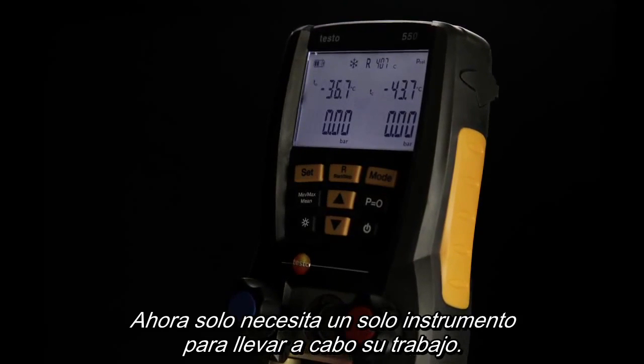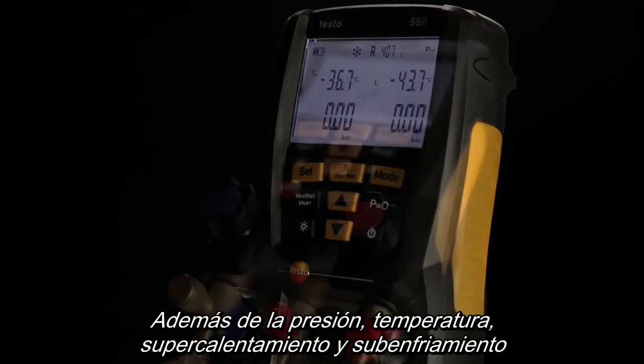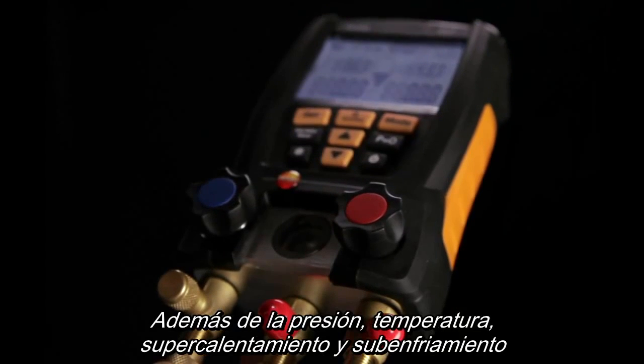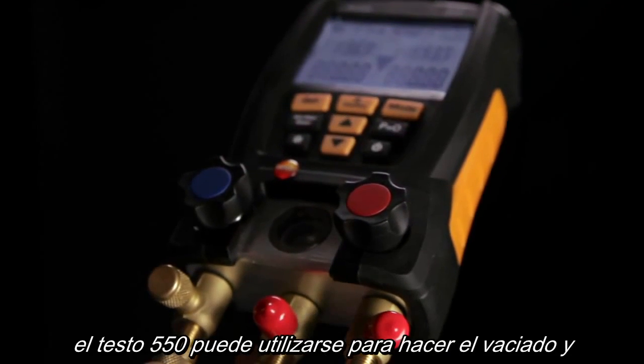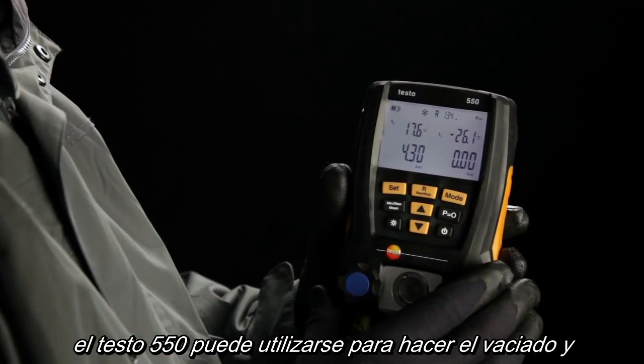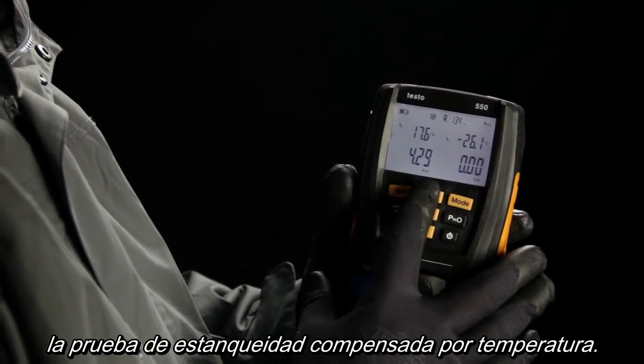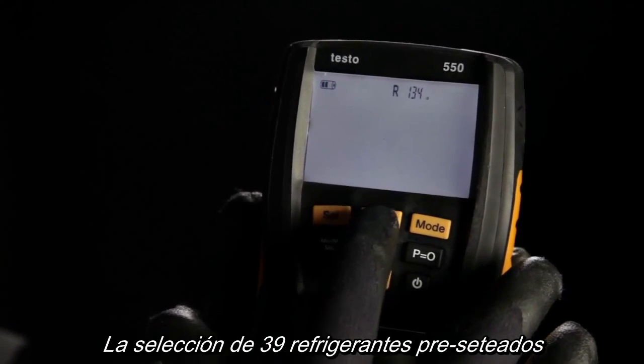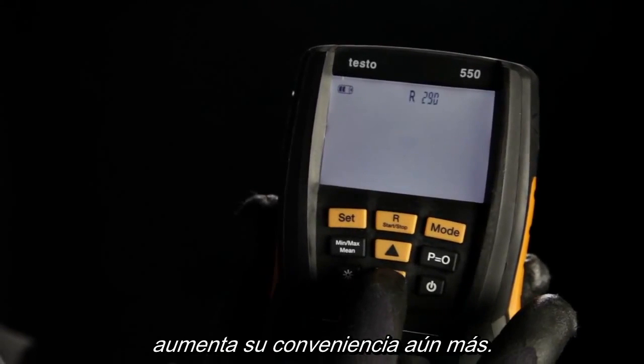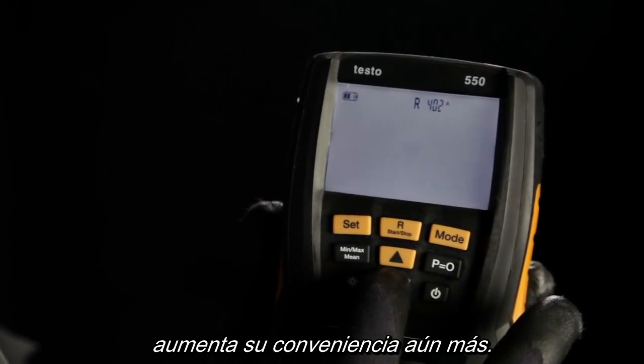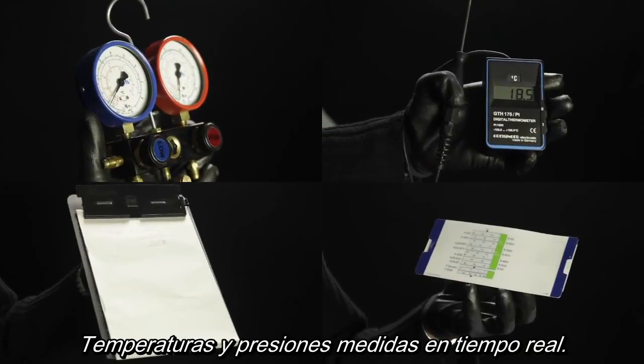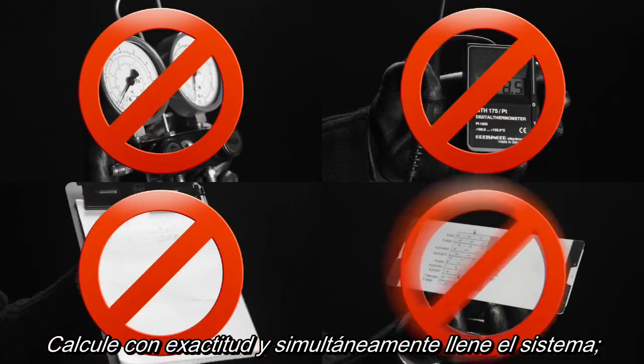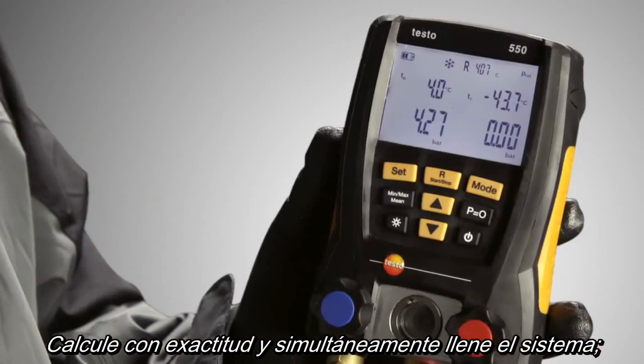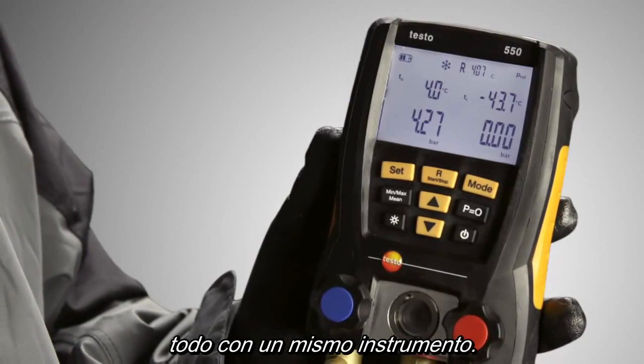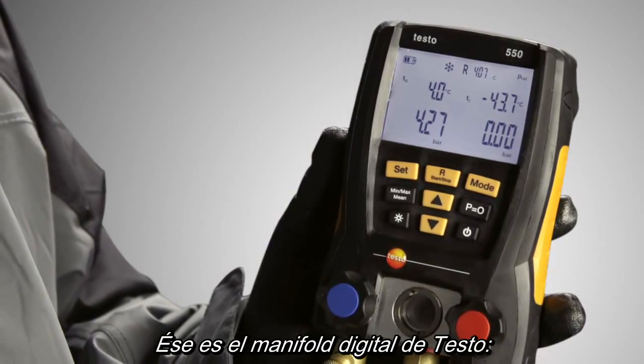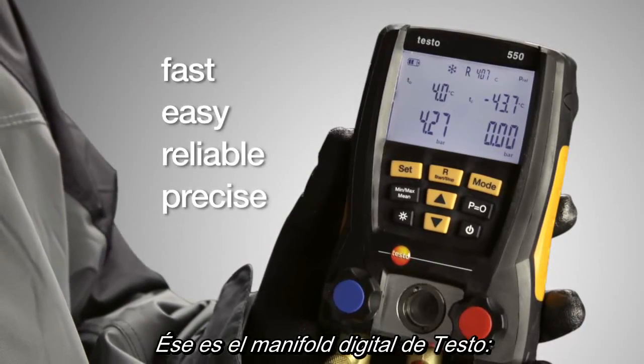You now need only one instrument to carry out your work. In addition to pressure, temperature, superheating and subcooling, the Testo 550 can be used for evacuation and temperature compensated tightness testing. The selection of 39 preset refrigerants increases convenience even more. Measure temperature and pressures in real time, calculate accurately, and simultaneously fill the system, all with a single instrument. That is the digital manifold from Testo.